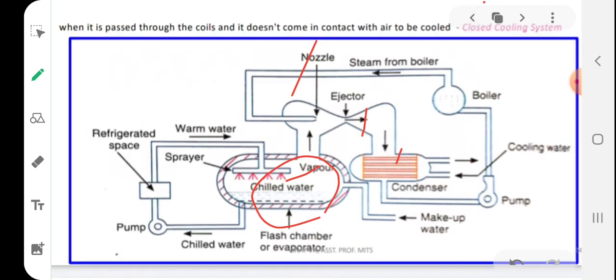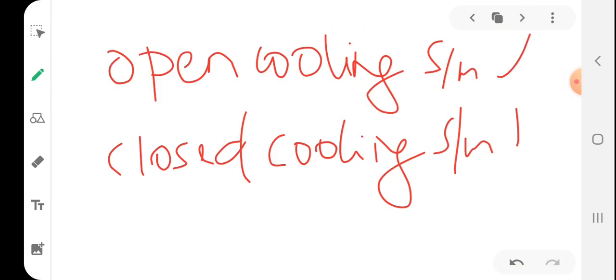Okay, so when chilled water from the flash chamber is directly used in the form of spray for cooling the air, it is called an open system. When it is passed through coils and doesn't come in contact with the air to be cooled, it is a closed system. Our aim is to cool some atmosphere or some space, right? So if the chilled water directly comes in contact with the air of that space, it means an open cooling system. When it is not in contact with the air directly and is passed through some coils, such a system is called a closed cooling system. So that is the difference between open cooling system and closed cooling system.